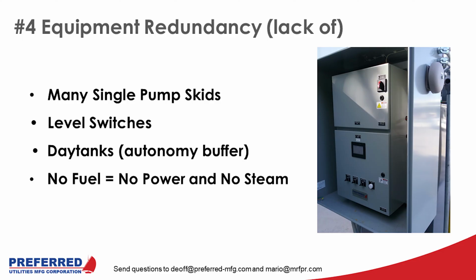And I want to mention that many of the systems are mission critical applications in the sense of, for example, healthcare and pharma industry, which require autoclaves for sterilization purposes. Some of these autoclaves are electric, but most of them are steam driven, and the boilers need the fuel. And if they are electric, the genset needs the fuel to provide the autoclaves with the power they require. So they really needed the equipment to operate, and not having redundancy was causing some issues for many end users.